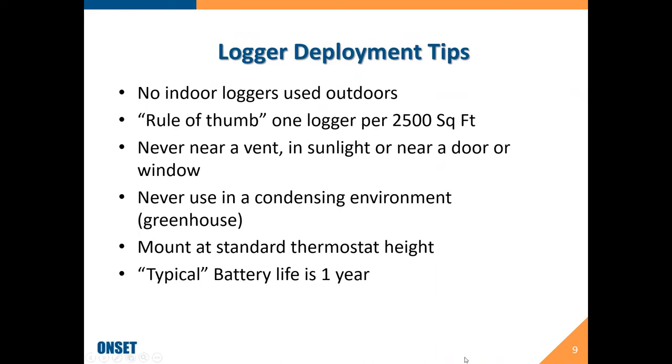Logger deployment tips. As far as using indoor loggers outdoors, that's a no-no. Indoor loggers are not protected against moisture falling, rainfall, that kind of thing, condensation. Never use an indoor data logger to measure outdoor temperatures. Rule of thumb for an average logger is 1 logger per 2,500 square feet. So if you're measuring a large area, you need to know whether this logger will give you the accurate readings.